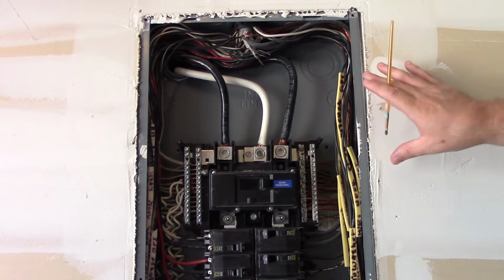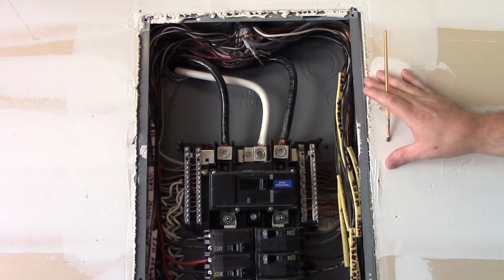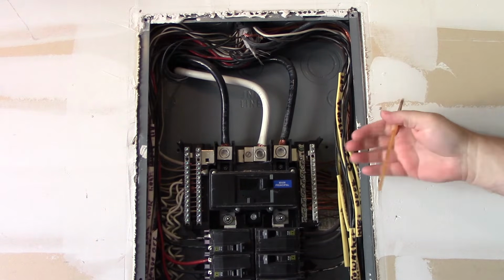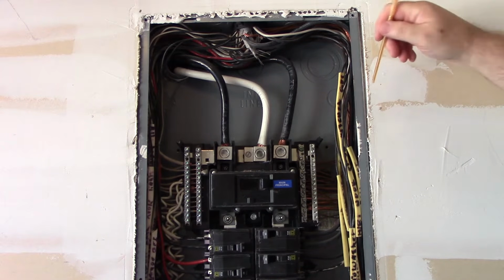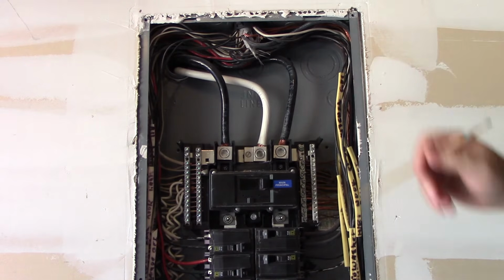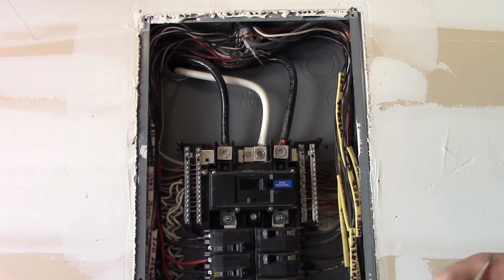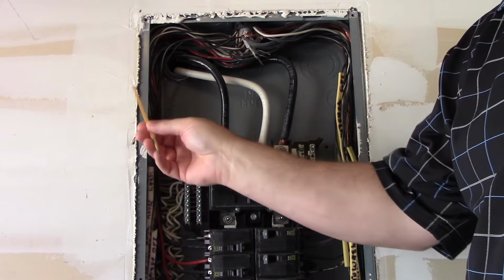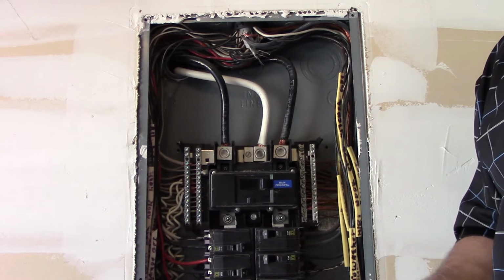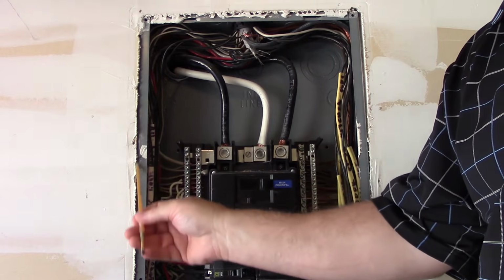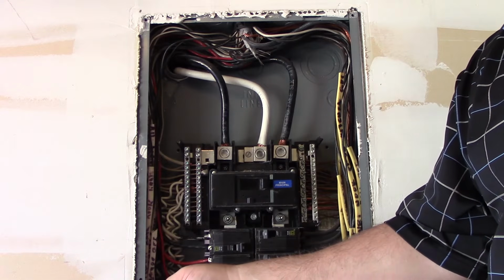Now, if this was a combustible material like wood, then it'd have to be flush. Okay, this panel would have to be flush. Okay, we don't want any embers to get around the side of it and get into the combustible material, which brings us to the next thing. If you're also doing a municipal inspection, you're not going to tell this on a rough-in, but you will on the final. You want to make sure that the gap around this panel does not exceed 1/8 of an inch.